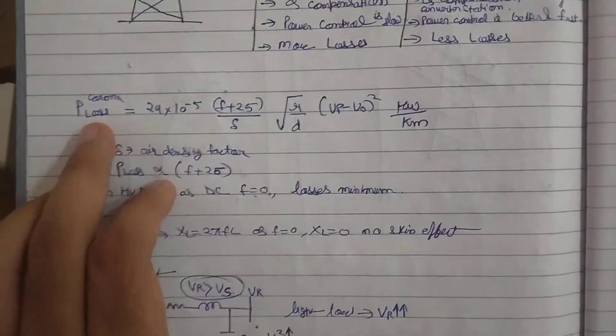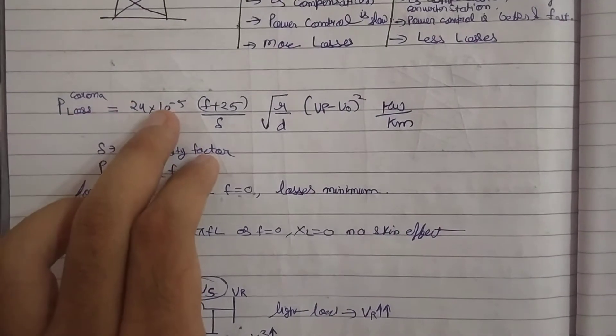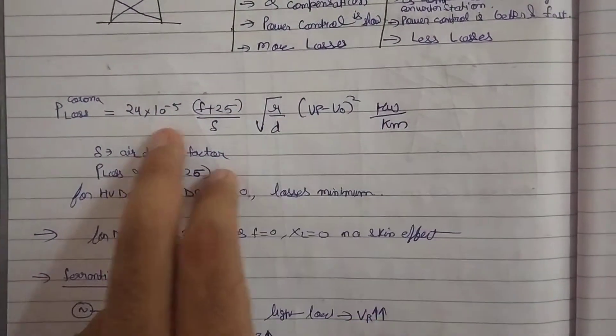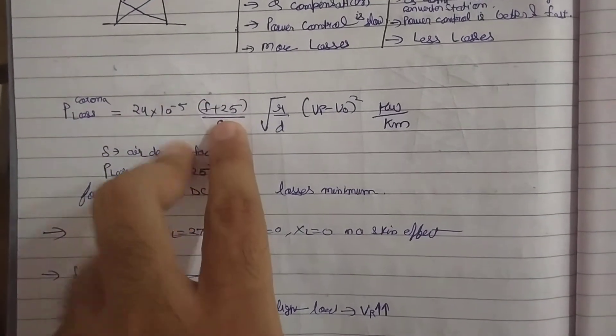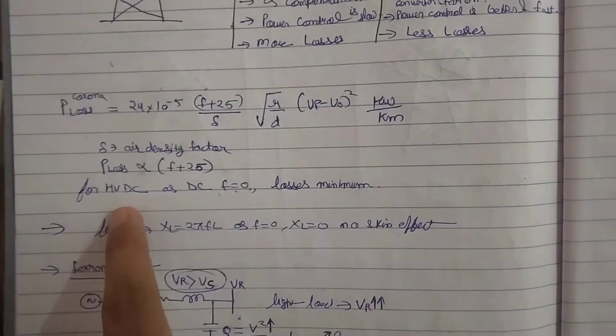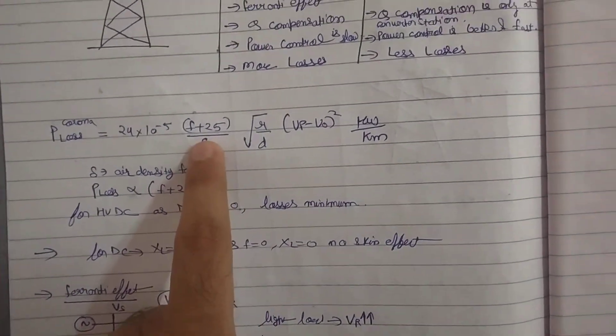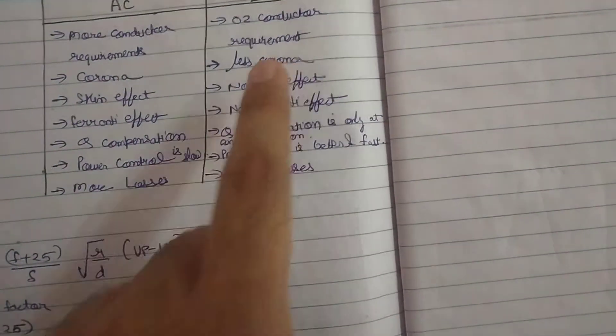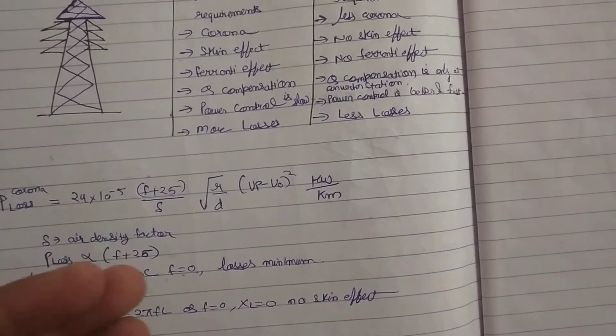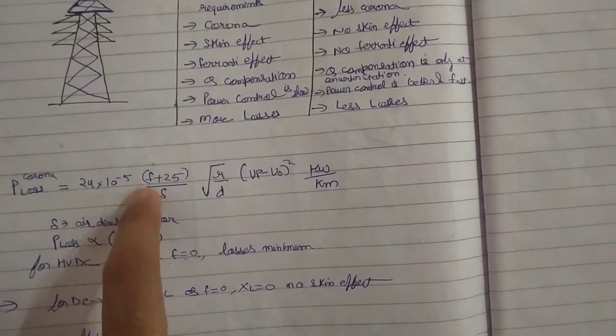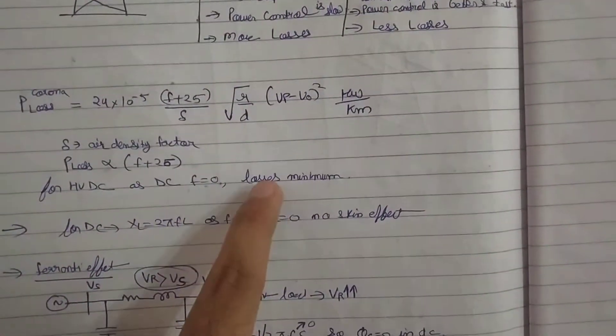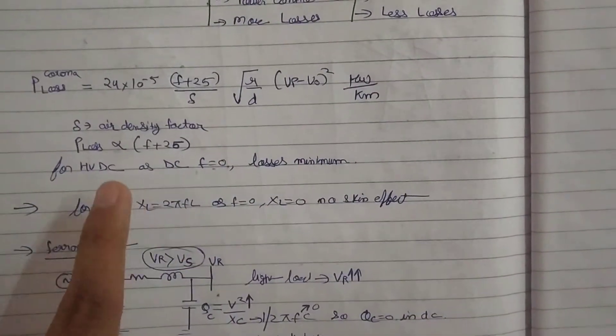If I talk about corona loss, the formula is 24 × 10⁻⁵ × (F + 25) / δ. This means corona loss is directly proportional to frequency. So for HVDC, frequency is zero, and the corona loss formula gives only the 25 component — not zero, but significantly less. Therefore, DC has less corona loss.